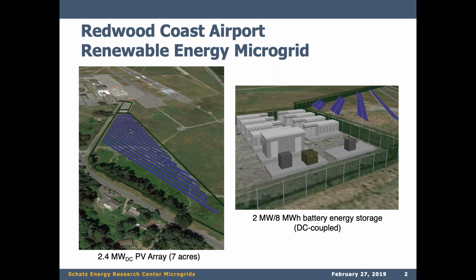That large 2.4 megawatt array will be DC coupled to the battery storage — meaning it will be connected on the DC side of the batteries, on the DC bus — and that whole system, the batteries and PV coupled together, will have one set of grid-facing AC inverters. As Richard said, that turnkey system of PV and battery storage is being handled by Tesla.